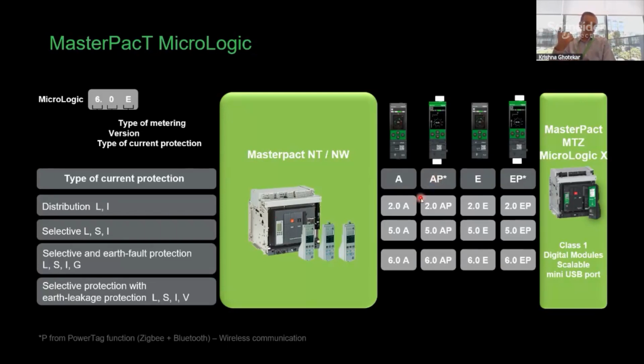So we have two types of trip unit. A type, which is the current metering plus the protection like overload, short circuit, and ground fault. E is with the energy metering like current, voltage, power, energy, frequency. Plus A and E also have maintenance indicators, let's say the contact wear and tear, the load profile, the per phase, and so on. Top it up, we can add on the wireless connectivity to it. By the way, A and E also have wireless, but it is NFC, near field communication, which I will discuss in the next few slides, which is mainly for the troubleshooting part.